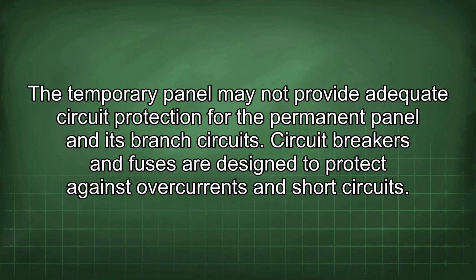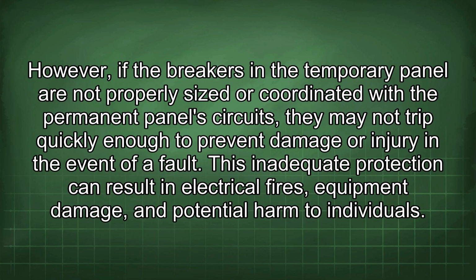The temporary panel may not provide adequate circuit protection for the permanent panel and its branch circuits. Circuit breakers and fuses are designed to protect against overcurrents and short circuits. However, if the breakers in the temporary panel are not properly sized or coordinated with the permanent panel circuits, they may not trip quickly enough to prevent damage or injury in the event of a fault. This inadequate protection can result in electrical fires, equipment damage, and potential harm to individuals.